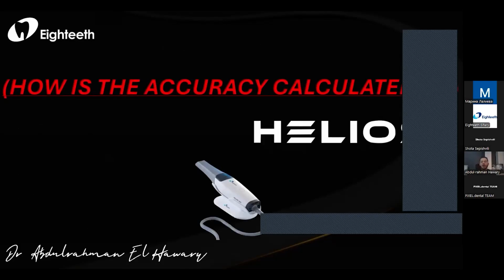So we have talked about the accuracy, right? We have talked about the accuracies, for example, 16 microns for the Helios 700, but we need to understand how the accuracy is calculated. It's called the full arch accuracy of 16 microns, which means that the maximum amount of deviation over a whole arch is 16 microns. This is for the Helios 700, okay? The maximum amount of deviation over the full arch is 16 microns.